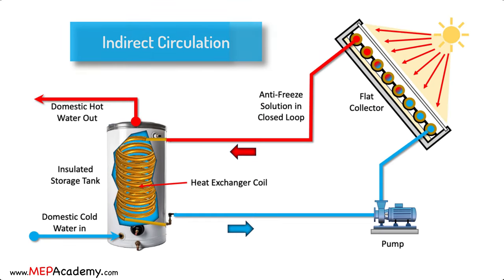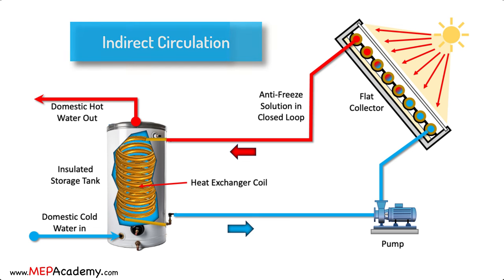Indirect circulation systems, also known as closed-loop systems, use an intermediate heat transfer fluid to transfer thermal energy from the solar collectors to the water in the storage tank. This allows them to operate in colder climates without the risk of freezing.